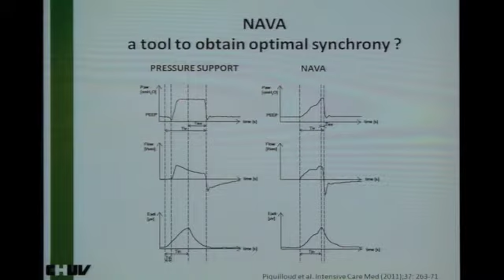We see that during pressure support, we have a delay between the beginning of the patient's inspiratory effort and the beginning of ventilator-delivered pressurization that disappears, or mostly disappears, during NAVA. And we see that during pressure support, we have an excessive time of pressurization from the ventilator in comparison to the neural inspiratory time, which is reduced during NAVA.